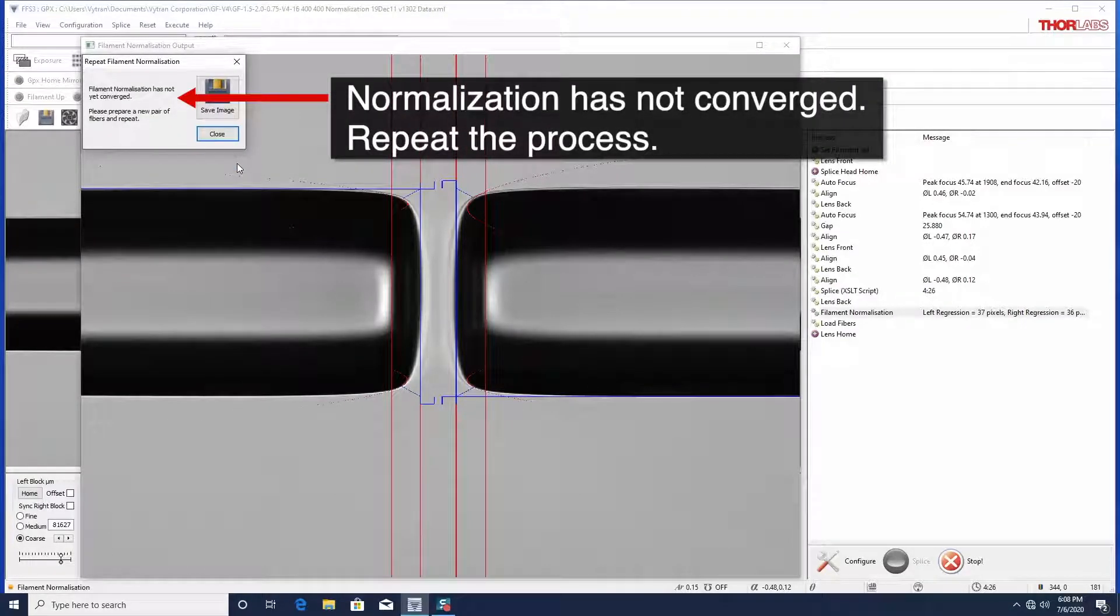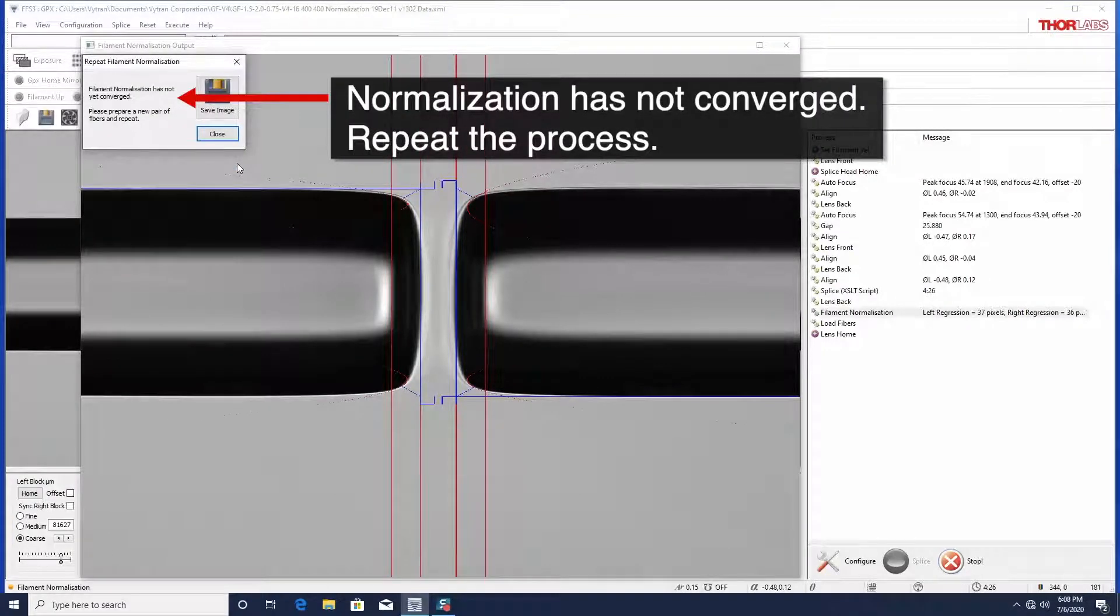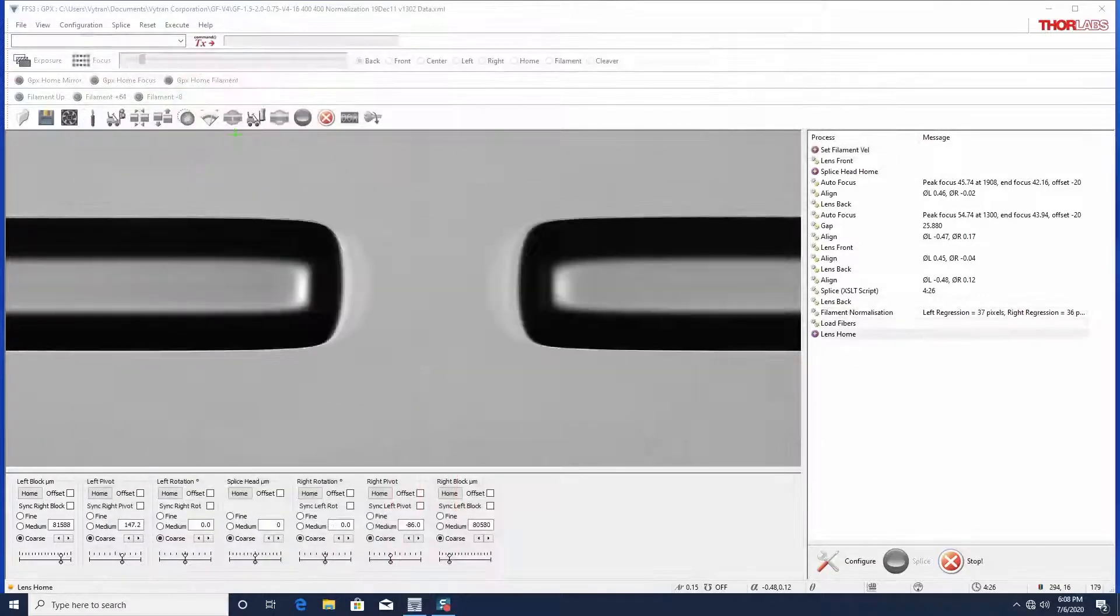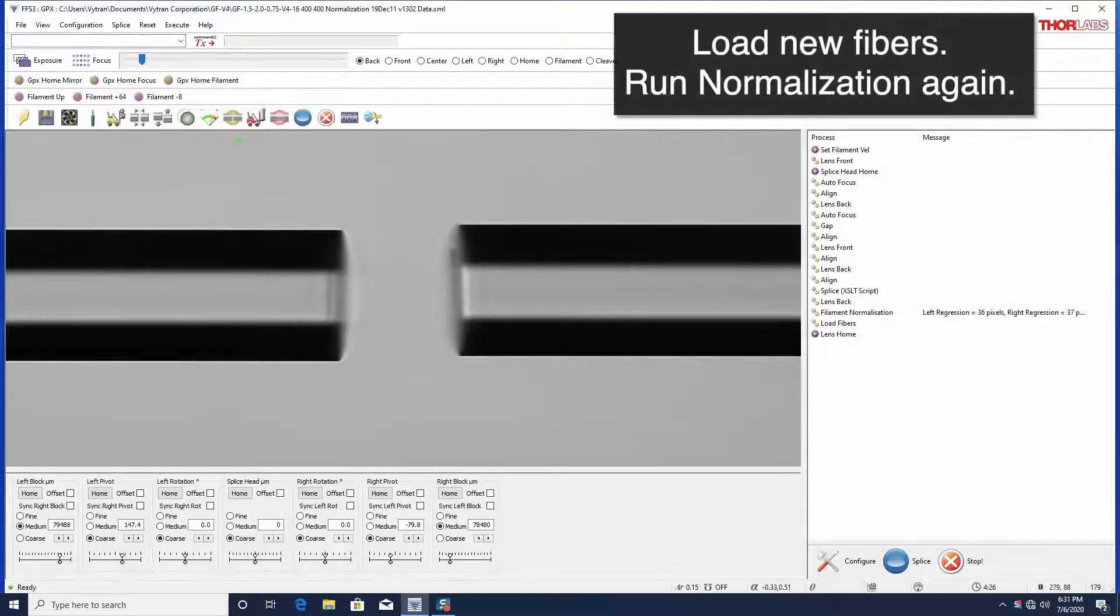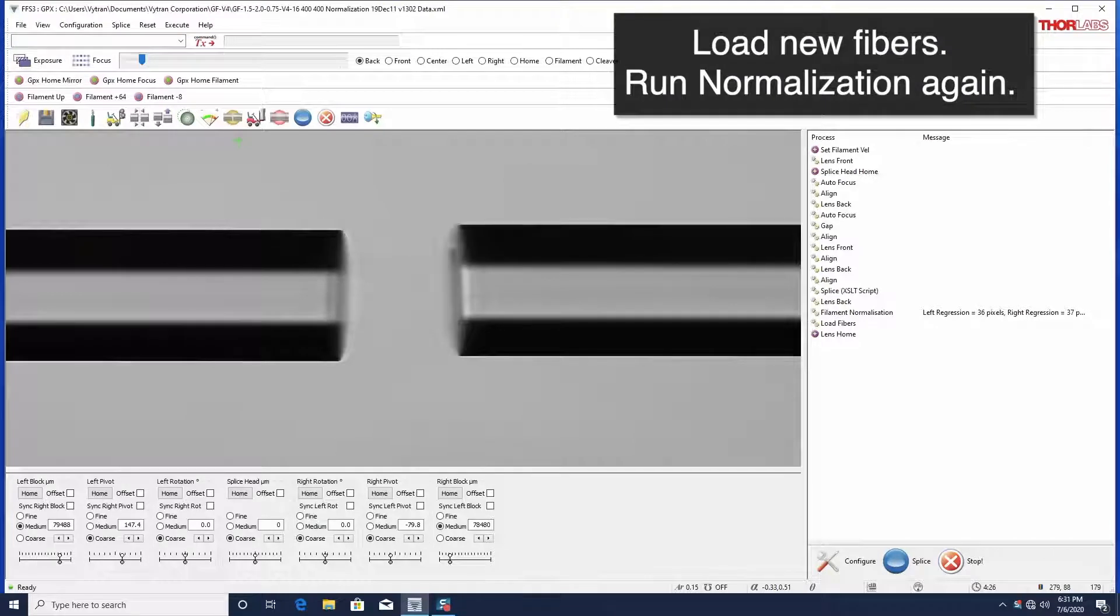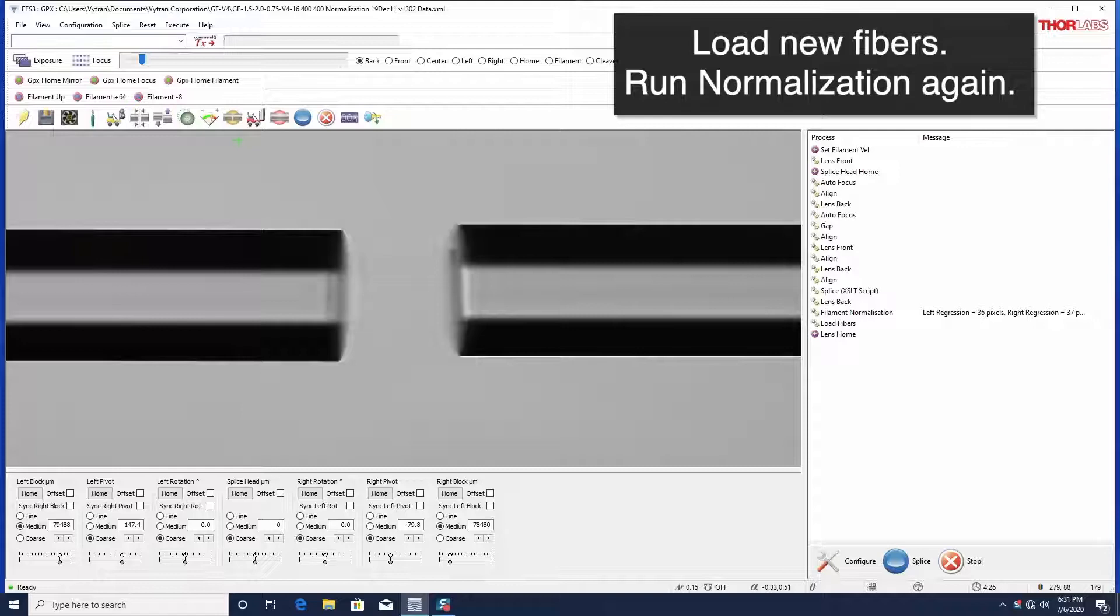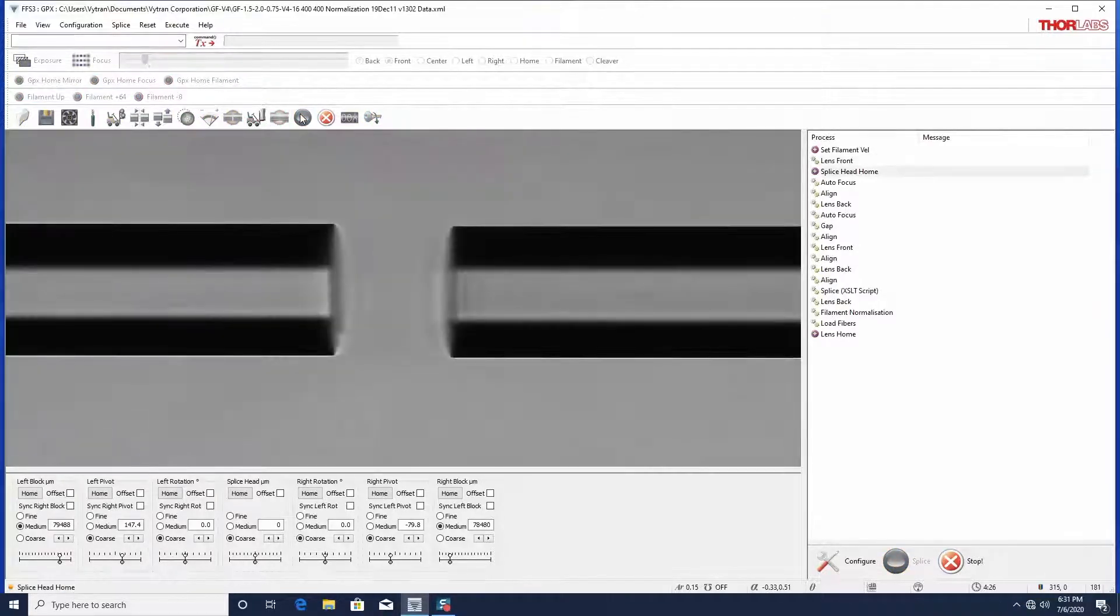It may take a few iterations for the normalization process to converge. To run the normalization process again, simply take out the fibers, remove the rounded ends, and prepare two new flat cleaved ends. These can be reloaded into the unit to run the normalization process again.